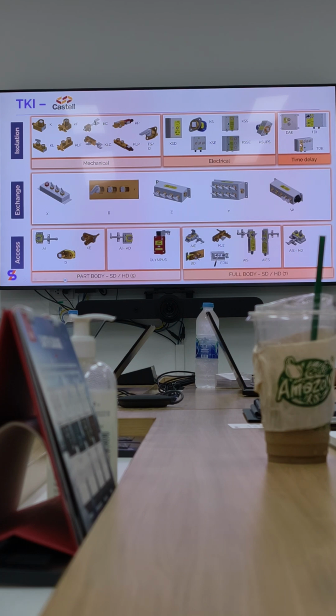Time delay is usually used in capacitor banks, because when we isolate the power, the capacitor bank still stores energy. We need a certain time for it to safely discharge, so we use the time delay. Let's say the capacitor bank takes 10 minutes to discharge - we set it to 10 minutes. After 10 minutes, there's a solenoid in the back that releases the key. Then you can turn and pick up the key to do the maintenance. Otherwise, if you don't have this, you might go in thinking it's safe, but energy is still stored, and you'll get shocked. Very dangerous. So this is the situation where time delay is used.